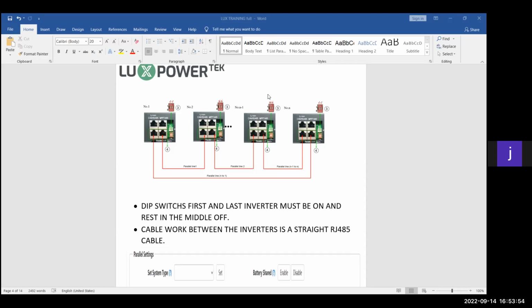All you're going to have to do is tell the inverter, let's say this was a 3-phase setup, so let's say this is your first phase, your second phase, and your third phase. Then you tell this inverter your R phase, your S phase, and your T phase. And then you can tell the fourth one you are one of the other phases as well. So this could be your T phase, for example, there's 2 inverters, and this could be R and S phase. That depends on how you like your setup, but you can have 4 inverters in a 3-phase system, 5, 6, depending on how you'd like to configure it. But yes, you can have a 3-phase system with 2 inverters on one phase and one on the other phases. You just have to tell the inverter which inverter is working with which phase.